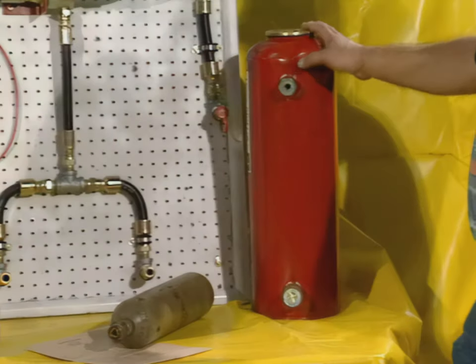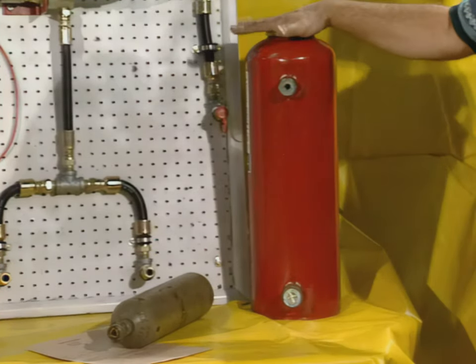The O-ring and the gasket on the bottom need to be kept greased. On a semi-annual inspection, this cap should be pulled, chemicals should be checked from the top as well as the bottom, and these rings should be greased. Let's talk about this other tank and the differences between the two.